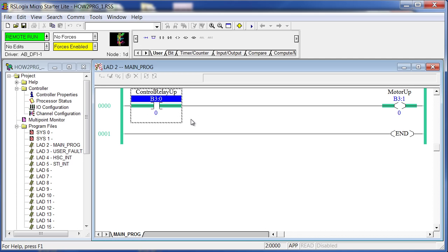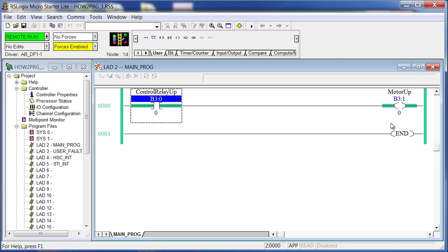Whether this is a contact from a real switch and this is a motor coil, the logic is the same — it looks the same. This is one of the advantages of relay ladder diagrams: they're so visually similar to electrical diagrams. I'm going to go back offline because I'm nowhere near done. I just wanted to show you that whether you use an actual field device or just toggle a bit, everything in the PLC happens entirely in memory — in the data table.